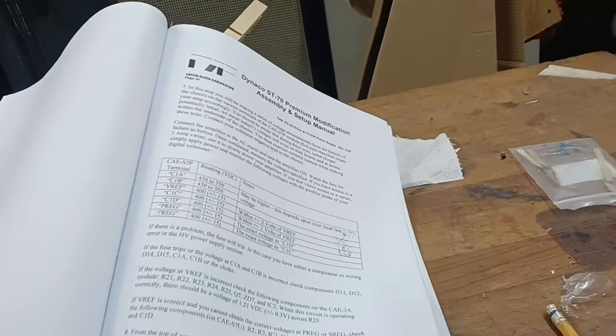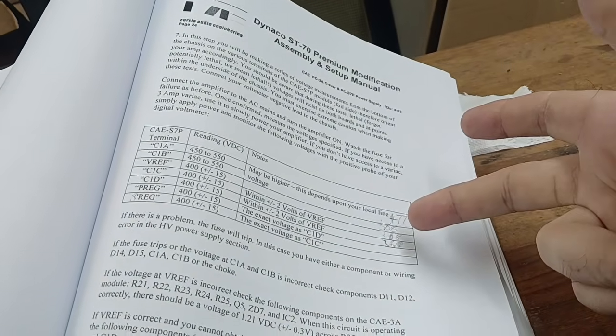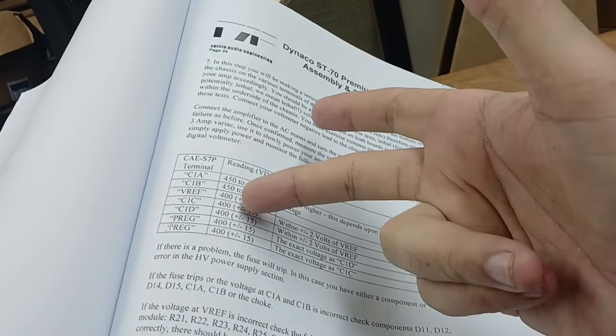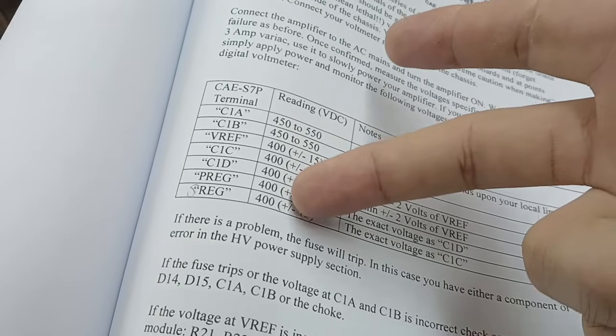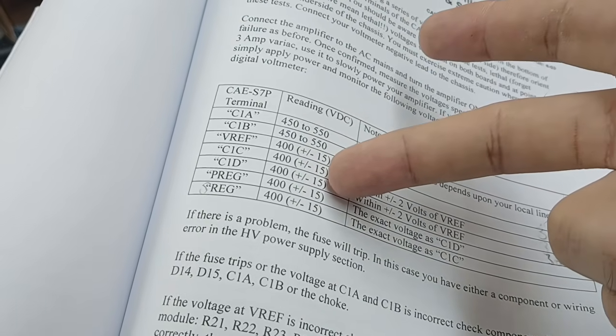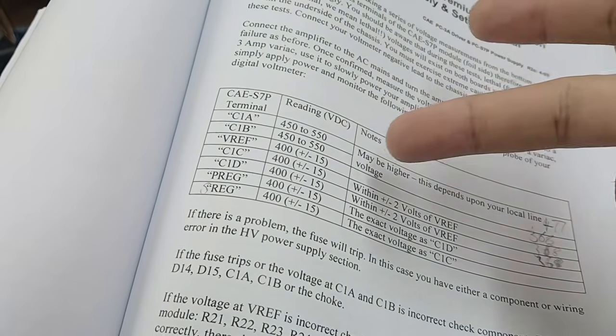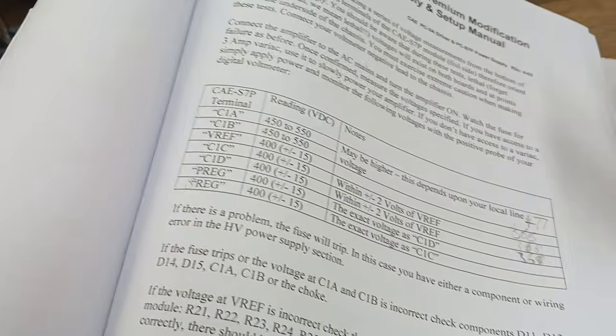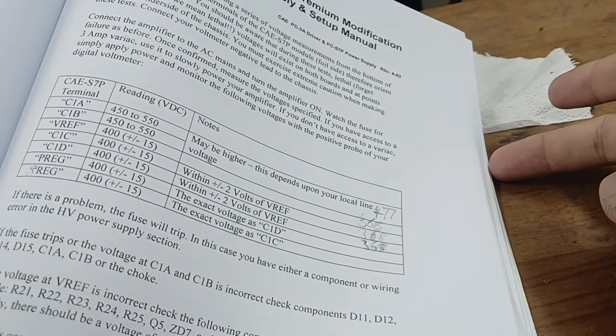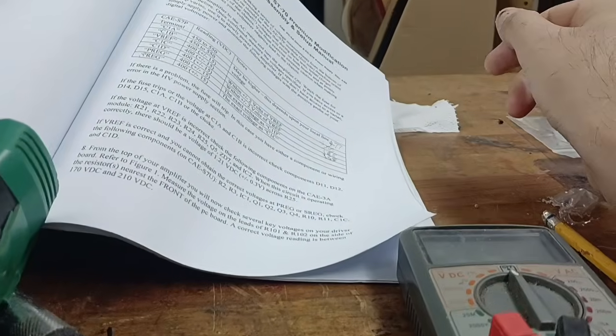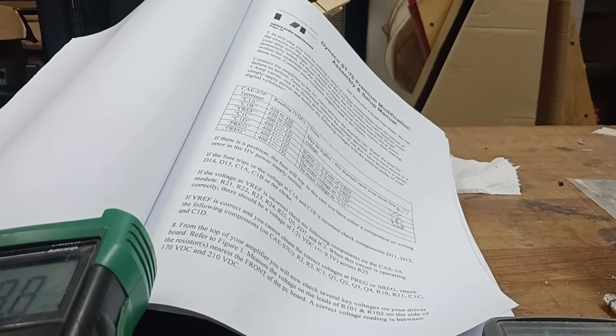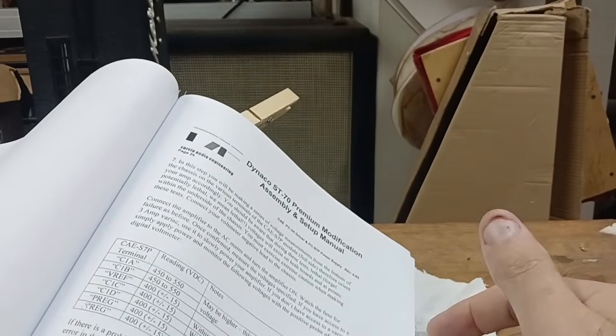My concern right now is that all these voltages are on the low side. They're listed at 400 plus or minus 15 volts, so let's say the lowest should be 385. I'm getting 368. Now, my line voltage from the wall is 117, and this whole setup may be designed for 120, so I don't know why everything is on the low side.